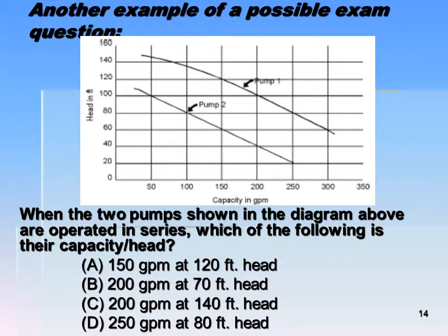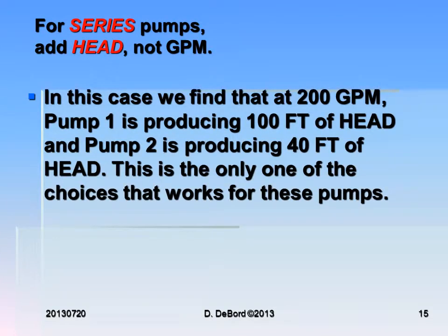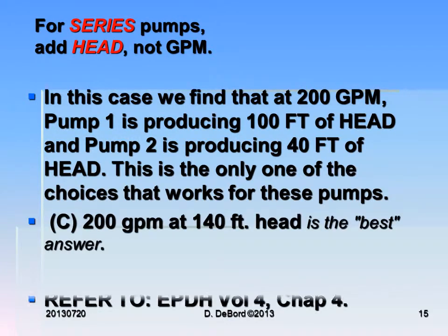At 200 GPM, we have 40 feet of head from one pump and 100 feet of head from the other, so that's 140 feet of head — so it's not B. At this point we've eliminated everything else, so what remains must be the answer. We find that at 200 GPM, pump 1 is producing 100 feet of head and pump 2 is producing 40 feet of head. That's the only choice that works for these pumps in series — answer C: 200 GPM at 140 feet of head is the best answer. None of the other choices A, B, or D fit the pump profiles except for C.